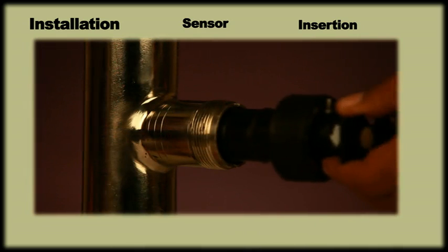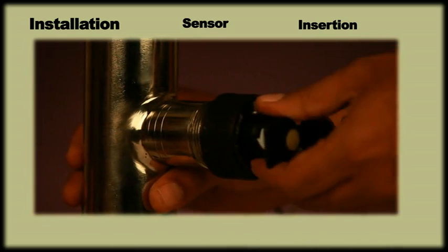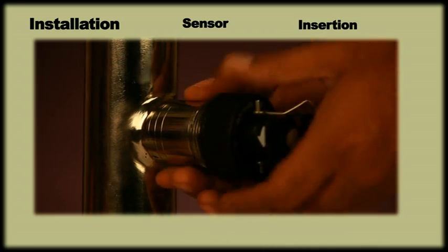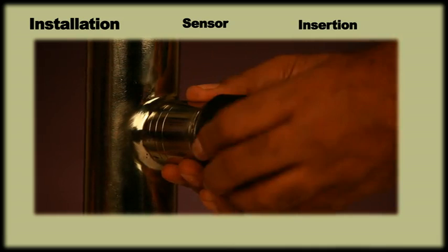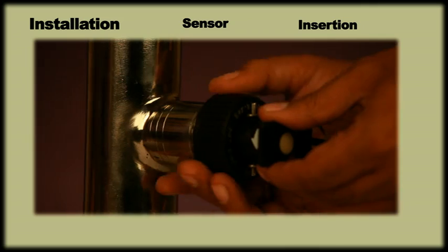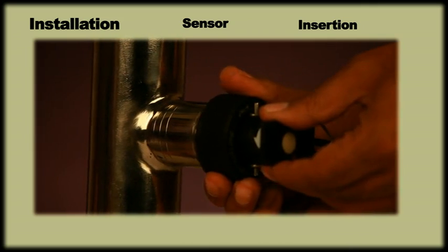Insert the sensor through the SS adapter in the correct orientation following the arrow mark. Slowly tighten the nut by gently rotating the sensor body. Ensure that the sensor gets properly locked in the notches of the adapter. Tighten the nut fully to finish the sensor installation.